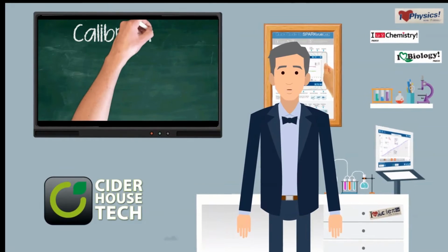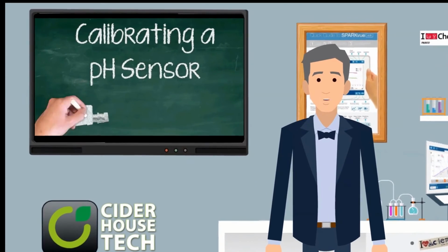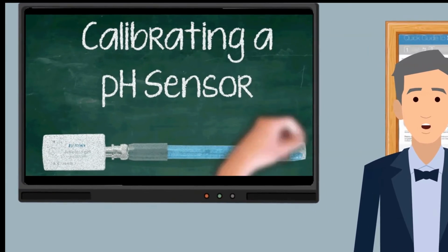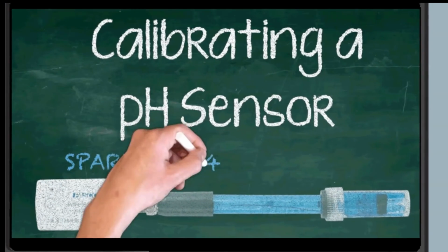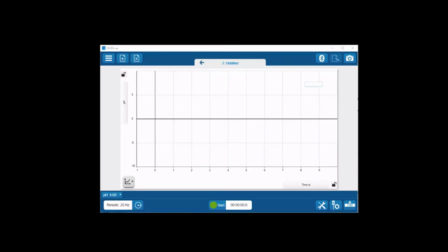This video from Pasco explains how to calibrate your pH sensors using SPARKVue version 4.4 onwards. If you have wireless pH sensors, you should not have to perform this calibration very often, as the sensor saves the calibration to its inbuilt memory. This is a video showing how to calibrate a pH sensor within SPARKVue 4.0 and beyond.